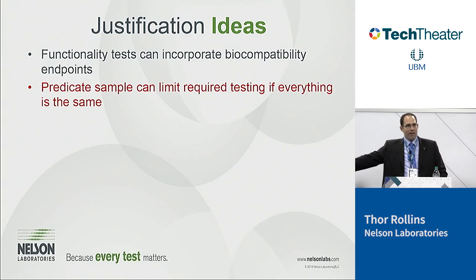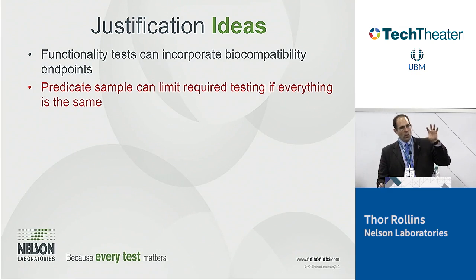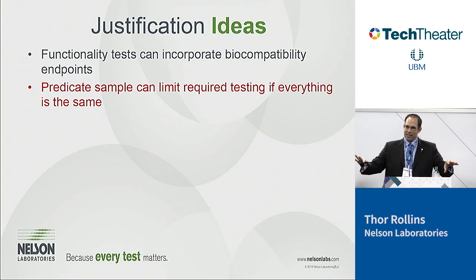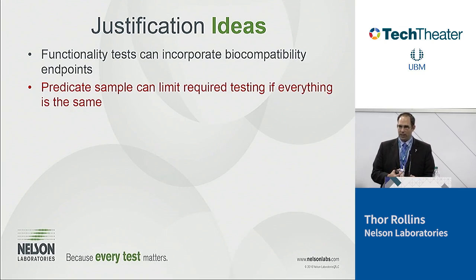You can use a lot of the information as a predicate device. Because remember, the FDA is concerned about materials and processing. So if you can show that materials haven't changed and processing hasn't changed, we've evaluated a lot of the endpoints that the FDA is concerned about with biocompatibility. So there are ways we can justify out of testing by evaluating these endpoints with a predicate device. If you make a device that's similar to the device you're trying to get a 510(k) for, then we can get through a lot of this assessment without having to do testing.